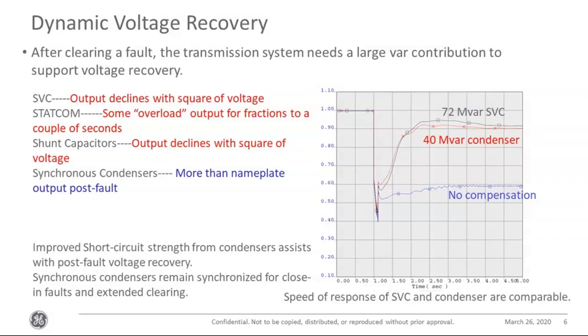Generally, this improved short circuit strength that comes from the synchronous condensers also helps with the post-fault voltage recovery. And also, there are some systems that require your reactive support devices to be online through severe faults or extended faults, and that is something that synchronous condensers are capable of doing. Right.